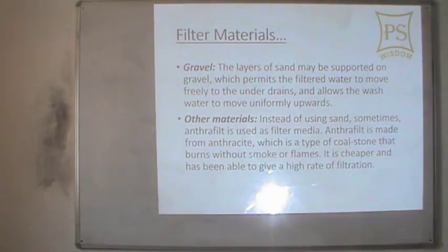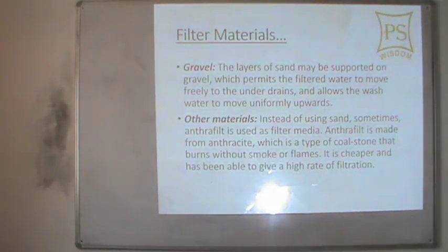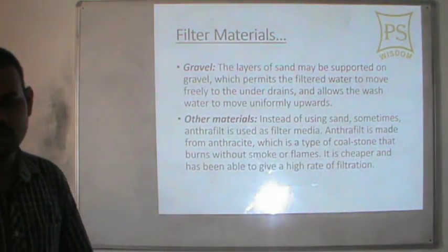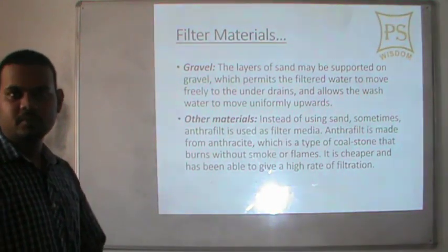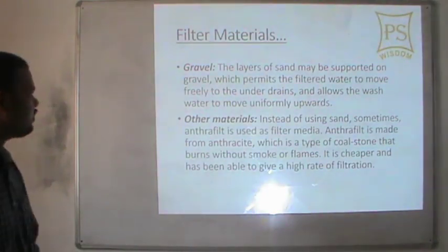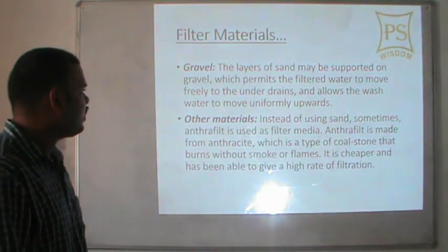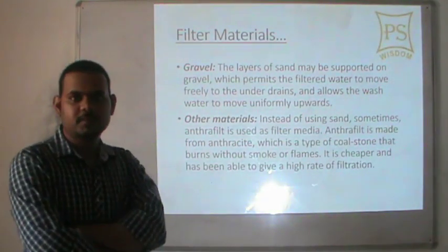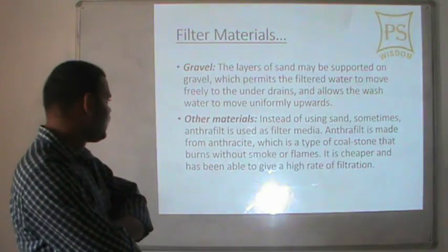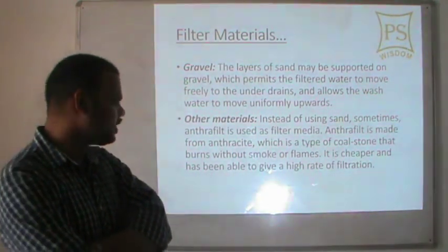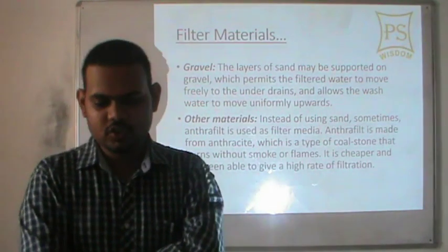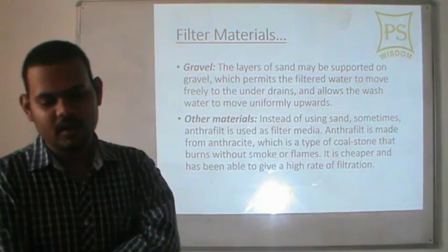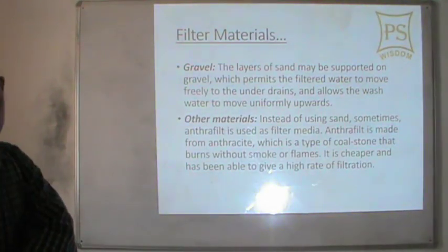Another filter material is gravel. The layers of sand may be supported on gravel, which permits the filtered water to move freely into the drains and allows the wash water to move uniformly upwards. Sometimes anthrafilt is used as a filter media instead of sand; anthrafilt is made up of anthracite, which is a type of coal that burns without smoke or flames. It is cheaper and has been able to give a high rate of filtration.